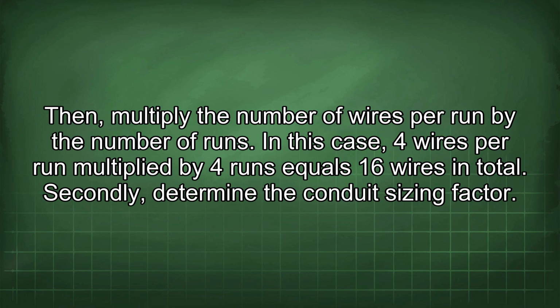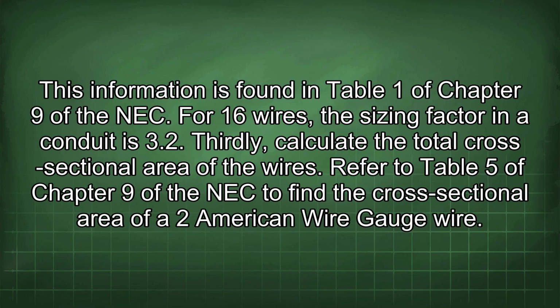Secondly, determine the conduit sizing factor. This information is found in Table 1 of Chapter 9 of the NEC. For 16 wires, the sizing factor in a conduit is 3.2.